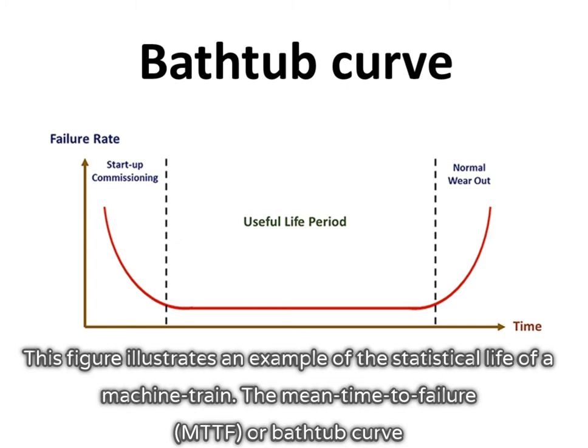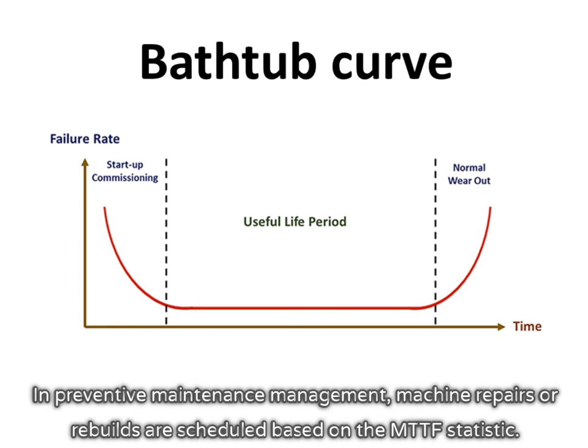This figure illustrates an example of the statistical life of a machine train. The mean time to failure MTTF, or bathtub curve, indicates that a new machine has a high probability of failure because of installation problems during the first few weeks of operation. After this initial period, the probability of failure is relatively low for an extended period. After this normal machine life period, the probability of failure increases sharply with elapsed time. In preventive maintenance management, machine repairs or rebuilds are scheduled based on the MTTF statistic.